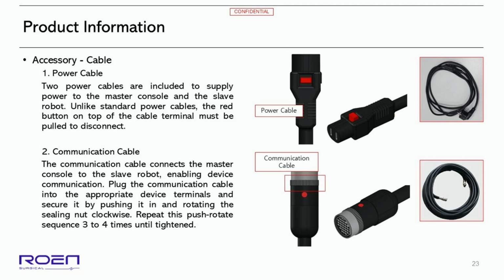The communication cable connects the master console to the slave robot, enabling device communication. Plug the communication cable into the appropriate device terminals and secure it by pushing it in and rotating the sealing nut clockwise. Repeat this push-rotate sequence 3 to 4 times until tightened.